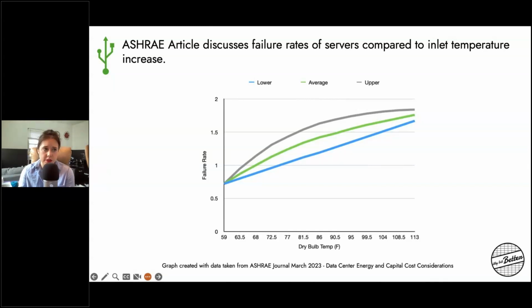It also looked at server reliability and IT equipment failure rates with increasing inlet temperature. To give you a baseline, during the first year servers are installed in a data center, they typically have a failure rate of about 5%. While this might seem high, it often results from out-of-the-box defaults and initial configuration issues. But over the next couple of years, failure rates only rise at a level of about 1%.